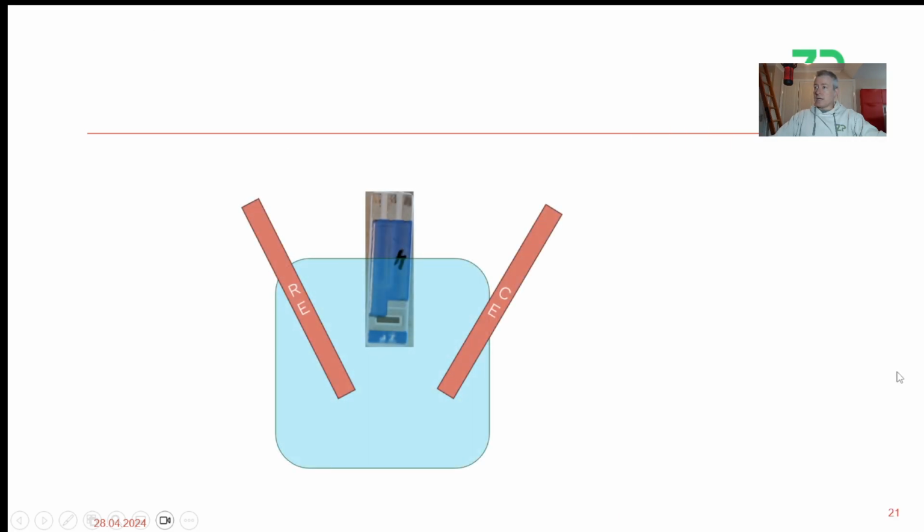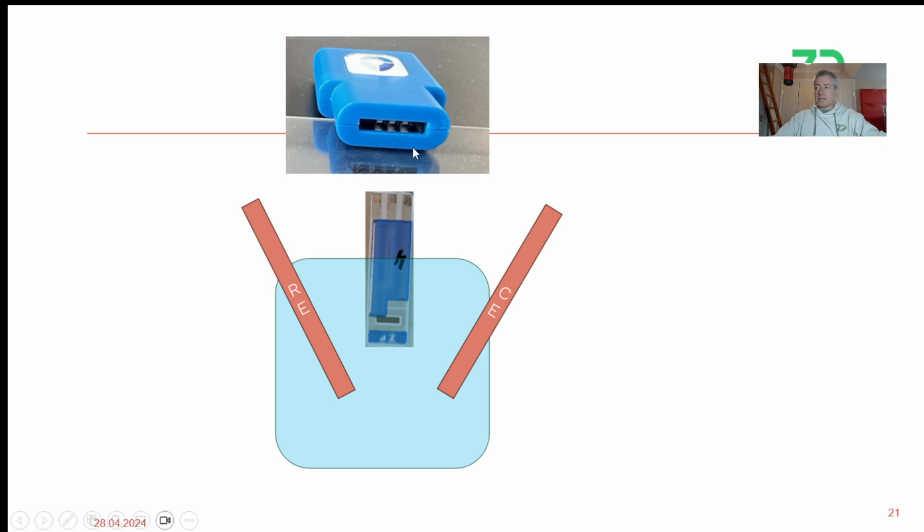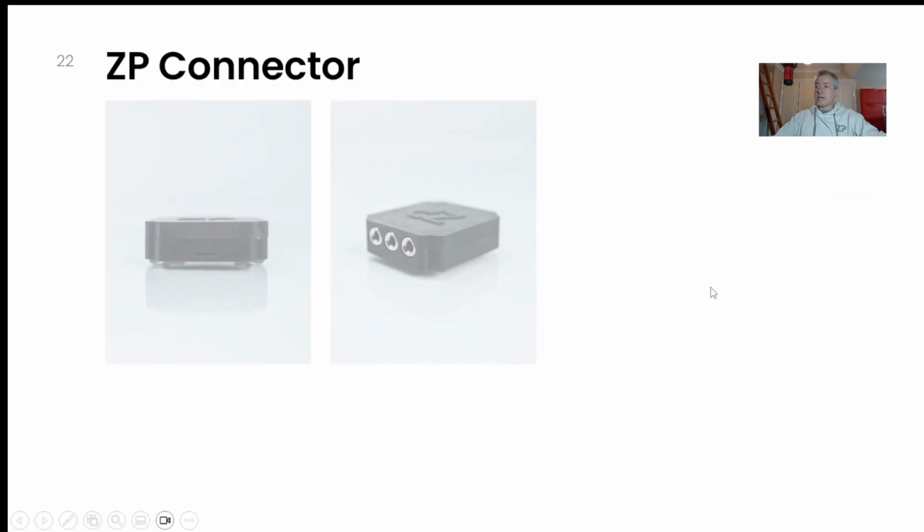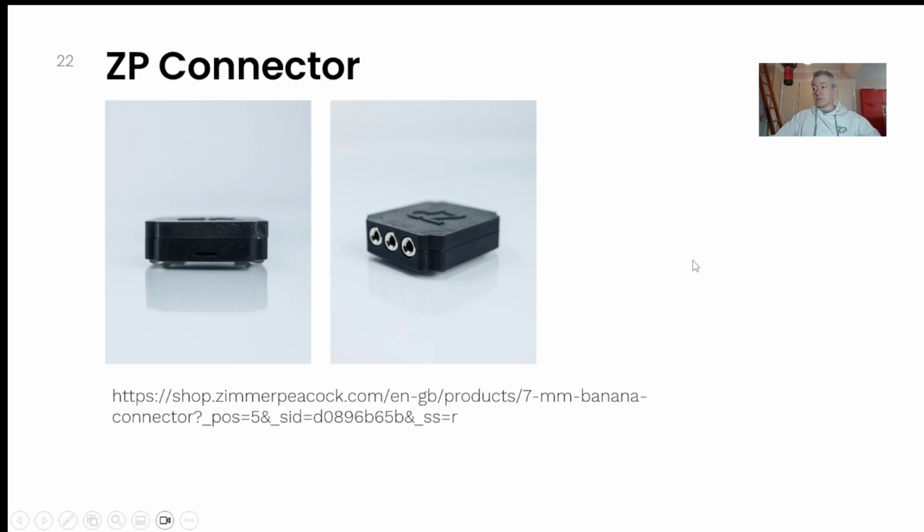They were using this particular connector, and I've had to get them off this connector because it comes from another company. It has a 10mm slot in there, but the SPEs here are 7mm, so it wasn't aligning correctly. So I advised them to get a different connector, which they actually went ahead and did. So thank you so much to them. The connector that I'm advising here has 2mm banana plug connectors, which works. And I have a strong suspicion from the photos that the person who's having problems at the moment also has 2mm connectors because of the potentiostat that they're using.